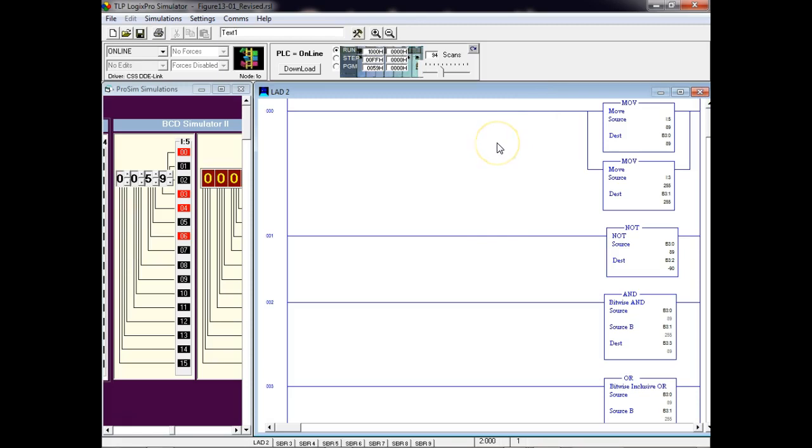So we use this all the time, but what it does is it allows me to bring a complete input port in and then strip off what I'm not interested in. Instead of me going out there on every one of those bits and putting a rung and an input instruction out there, I can go in and bring in a whole input port and strip off the bits that I'm not interested in. If I need the bits I'm not interested in to be ones, I'll use an OR mask. If I want the bits that I'm not interested in to be zeros, I'll use an AND mask.